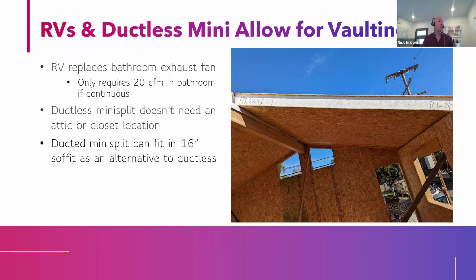So our bathroom has a vaulted ceiling, and the whole place has a vaulted ceiling, which is really nice for an ADU because it gives you the impression of more space. And of course, the ductless mini splits don't need an attic to run the ducts either. Even a ducted mini split can fit in a small soffit, and you can still vault the ceiling. Yeah, so the vaulted ceiling in this case has no means of reducing moisture, but the recovery ventilator in my mind is doing that job. It's continuously removing moisture, so there's no issue with it accumulating up there at the roof deck. Plus we've got balanced, neutral pressure, as opposed to some pressure pushing it up there.